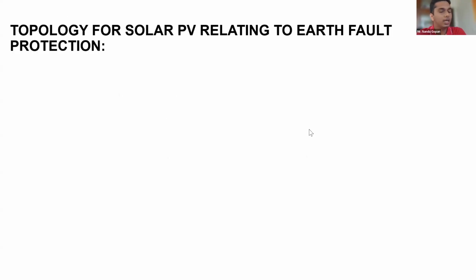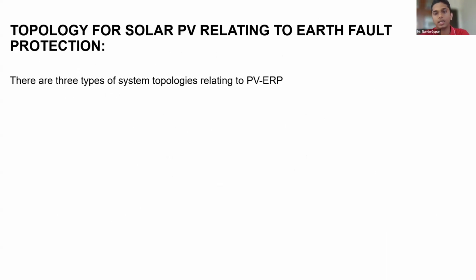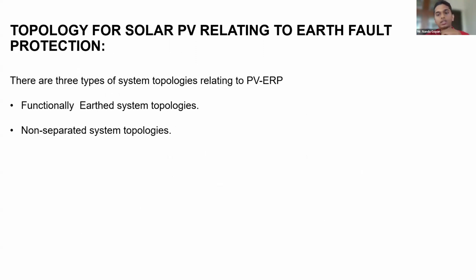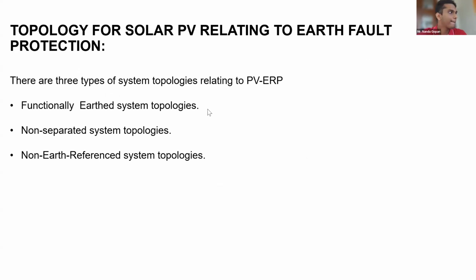So the topology is related to earth fault protection in a PV array. Basically, there are three types of topologies for earth fault protection. One is functionally earthed system topology. Another one is non-separated system topology, and the last one is non-earth referenced system topology. These three are the topologies related to earth fault protection in a PV system.